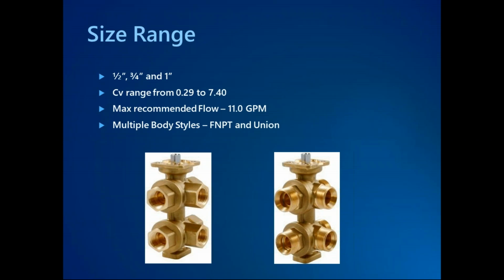And again, it's tied to getting independent temperature control for each room and doing that as efficiently as possible. So paring down the size of these zones makes sense when it comes to using 6-way control valves, hence the typical size restrictions. And towards the end here, we'll look at some solutions for higher flow applications, because a very large conference room or some other larger spaces may require a unique approach to tying these 2-pipe zones into a 4-pipe system. And then connection types on the market today, there are 2 main options, one being fixed FNPT ports on all 6 ports. The other is a union type of fitting on all 6 ports. It's more of a preference thing when it comes to one versus the other.